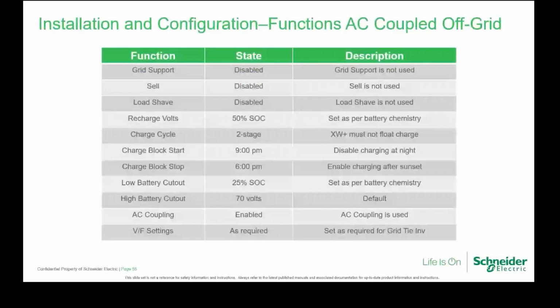When you're off grid, grid support is obviously disabled because you don't have any grid. Sell will be disabled, load shaving will be disabled. Recharge volts, same thing, state of charge, two stage for charge cycle. Charge block stop, doesn't really matter. Low battery cutout, state of charge or the equivalent voltage for the state of charge. High battery cutout, AC coupling has to be enabled, and voltage and frequency settings as required by the grid tied inverter manufacturer.